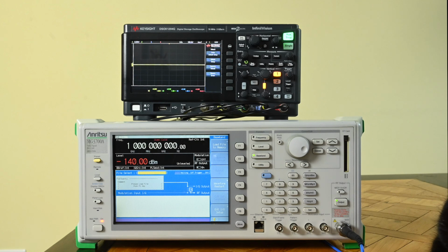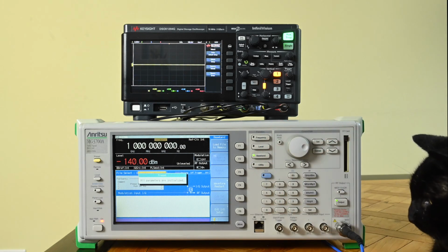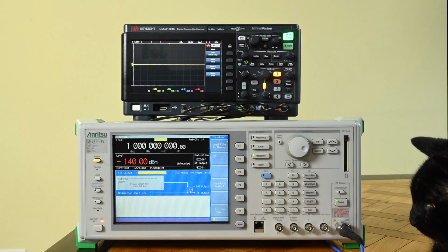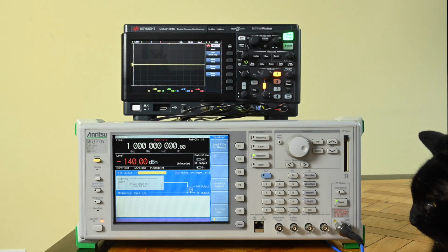But for this particular purpose today, I reset the whole device before I start. That's very simple. Actually, restarting is just going here. I tell it to restart everything, and that's it. Everything is initialized, so I start from a 0 condition here. I also see some warning here, oven cold. No worries about that. That is the crystal. The crystal is in an oven to keep it a bit more constant, and that oven is just a little bit cold still because I just turned it on. This will go away in a little moment, that warning.